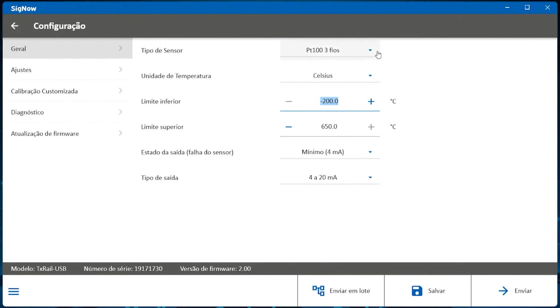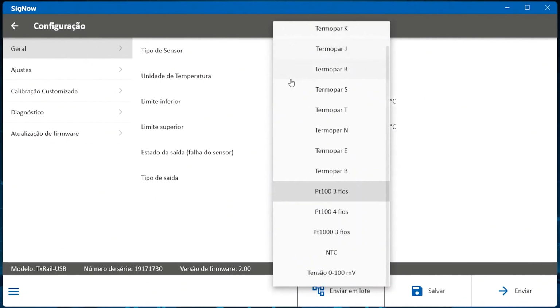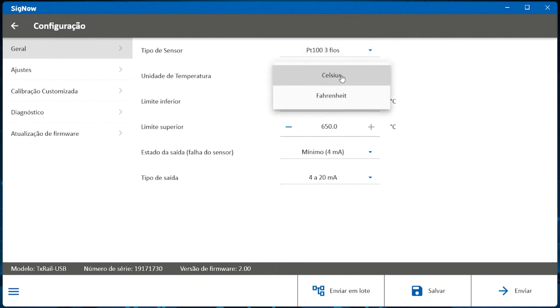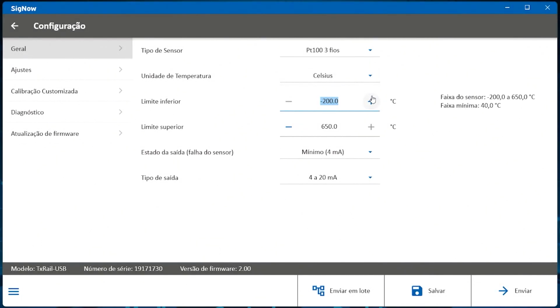The sensor type will be displayed, and there's a group of sensors that can be used in my device. I'm going to choose PT100 3-wire option. Here we have the quantity that I'm going to use in reading mode. I can decide whether the value will be displayed in Celsius or Fahrenheit. Each sensor has its own lower and upper reading limit. In this case, my lower limit of reading is -200 degrees Celsius and the maximum is 650 degrees Celsius.